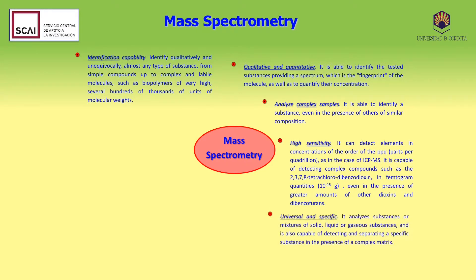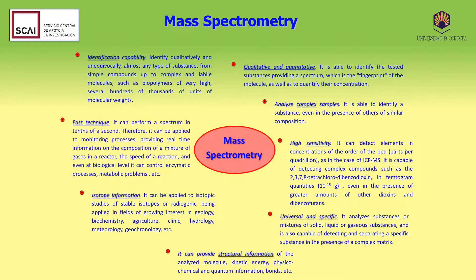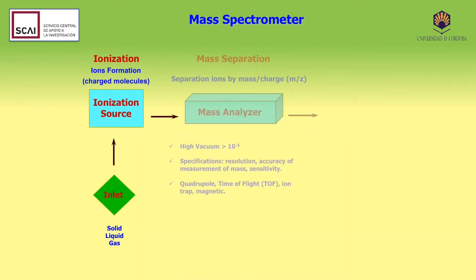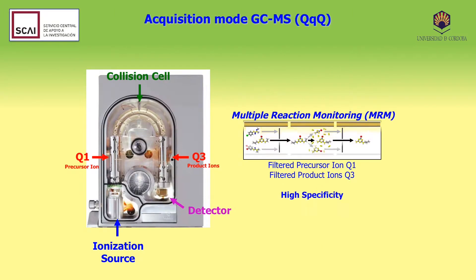Mass spectrometry can analyse complex samples, it has a high sensitivity, it is universal and specific, it provides both structural and isotopic information, and is a rapid technique. Mass spectrometers have three different parts: ions are produced at the ionisation source, then separated in the analyser, and the detector will identify and quantify the ions. The analyser used is a triple quadrupole, and the acquisition mode that we will be using is the MRM, multiple reaction monitoring, which provides a high specificity.